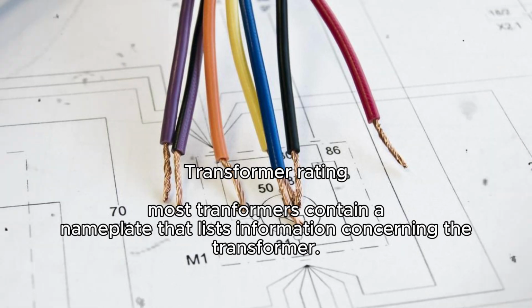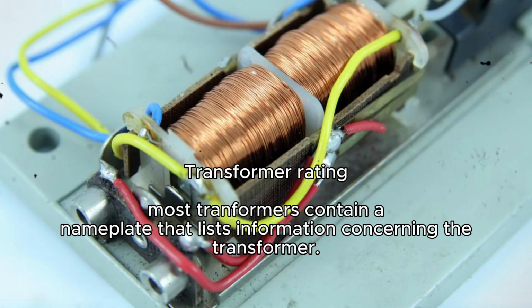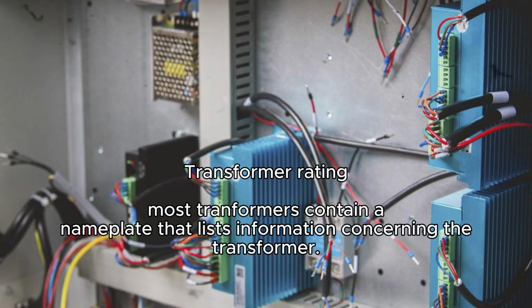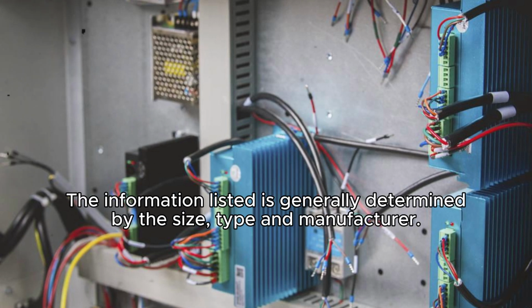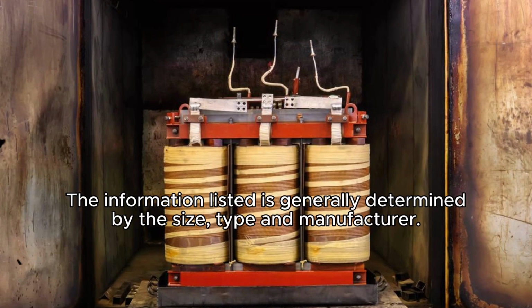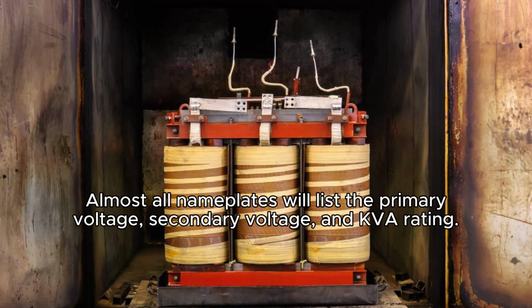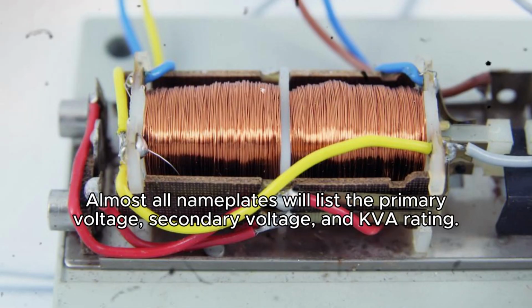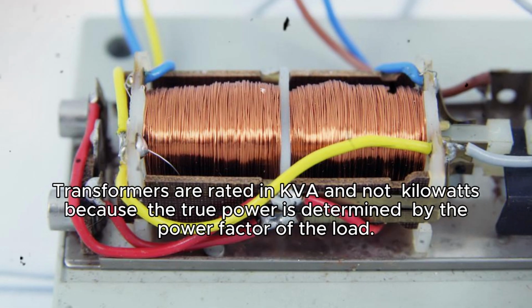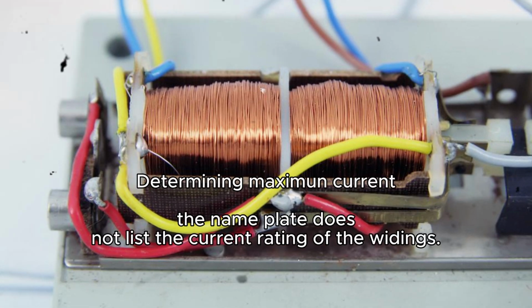Transformer rating. Most transformers contain a nameplate that lists information concerning the transformer. The information listed is generally determined by the size, type and manufacturer. Almost all nameplates will list the primary voltage, secondary voltage, and kVA rating. Transformers are rated in kVA and not kilowatts because the true power is determined by the power factor of the load.